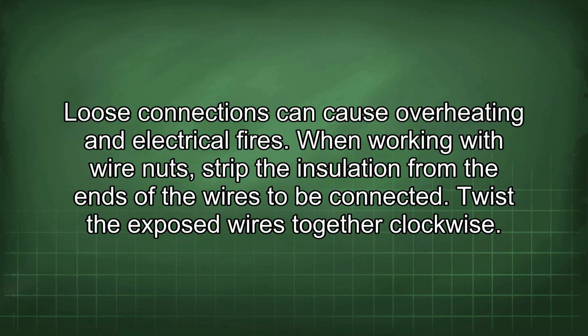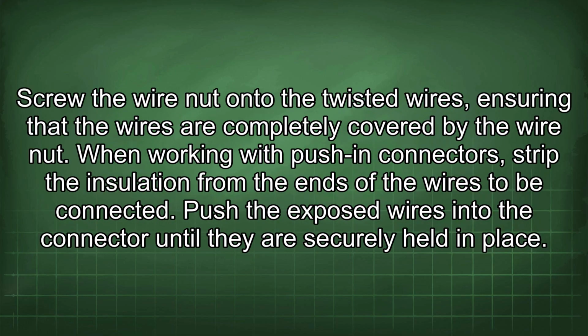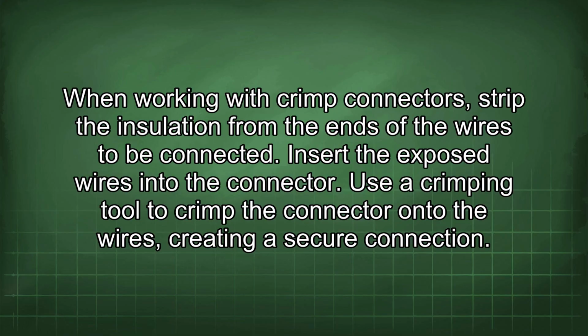When working with wire nuts, strip the insulation from the ends of the wires to be connected. Twist the exposed wires together clockwise. Screw the wire nut onto the twisted wires, ensuring that the wires are completely covered by the wire nut. When working with push-in connectors, strip the insulation from the ends of the wires to be connected. Push the exposed wires into the connector until they are securely held in place. When working with crimp connectors, strip the insulation from the ends of the wires to be connected. Insert the exposed wires into the connector. Use a crimping tool to crimp the connector onto the wires, creating a secure connection.